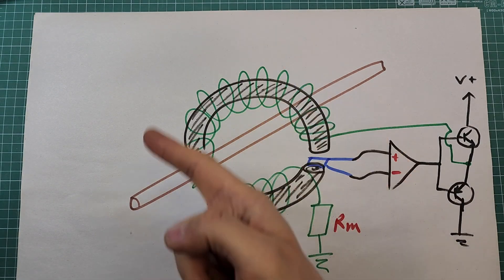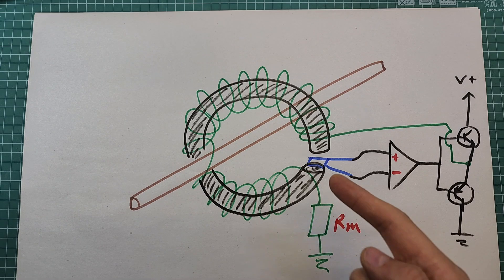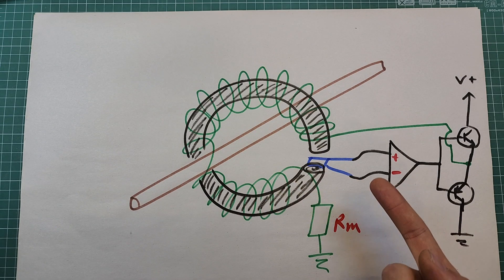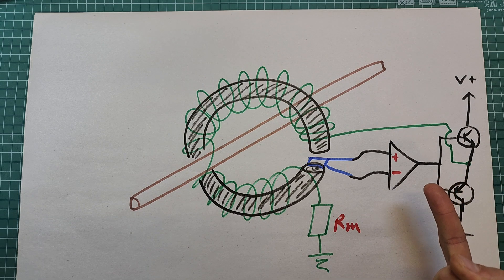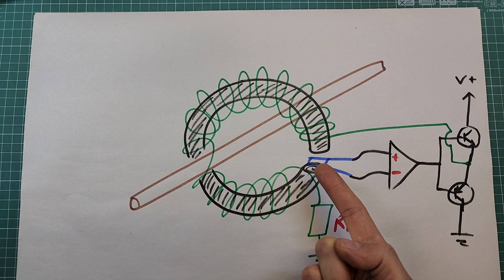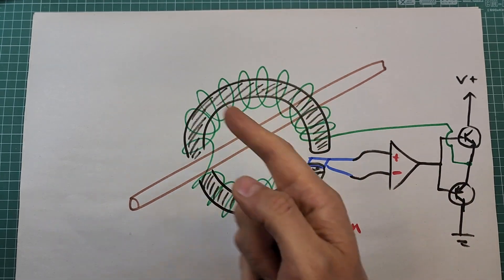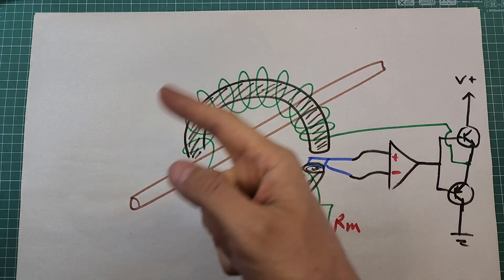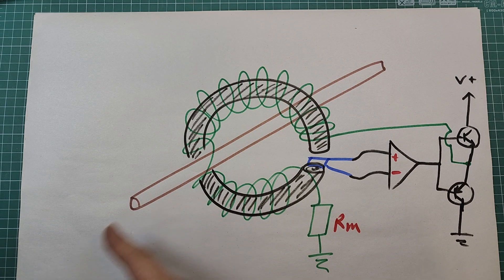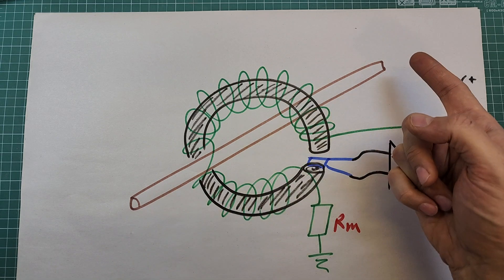In the closed-loop circuit, we wrap a wire around the metal ring and connect the end of the coil to ground through a resistor. We connect the output of the Hall effect sensor to an amplifier, and the output of the amplifier to a current-driving circuit. The amplifier is configured so that when the sensor output voltage increases, the current through this coil is adjusted in the appropriate direction so that the magnetic field produced by the coil cancels out the magnetic field from the current-carrying wire. We can then calculate the current by measuring the voltage across this resistor.